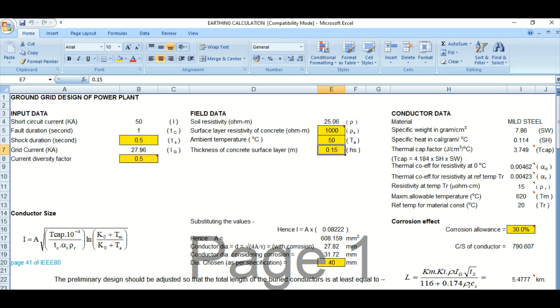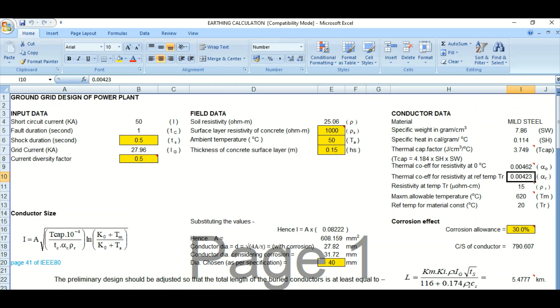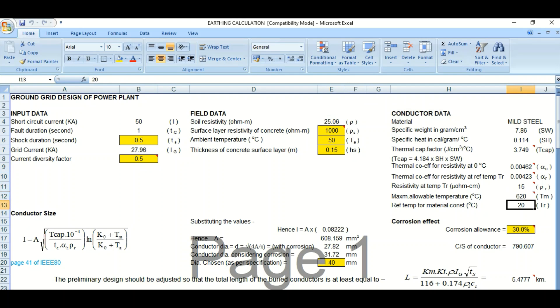Next is the conductor data. The material used is mild steel (MS) rod. The conductor parameters include specific weight, specific heat, thermal capacity factor, thermal coefficient of resistivity (alpha-0), resistivity at different temperatures, maximum allowable temperature, and reference temperature for material constant. All this conductor data is required for the calculation based on the material type.